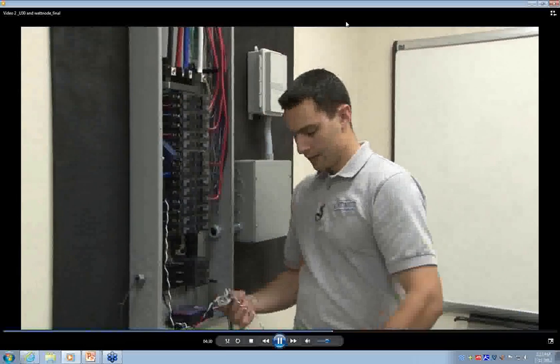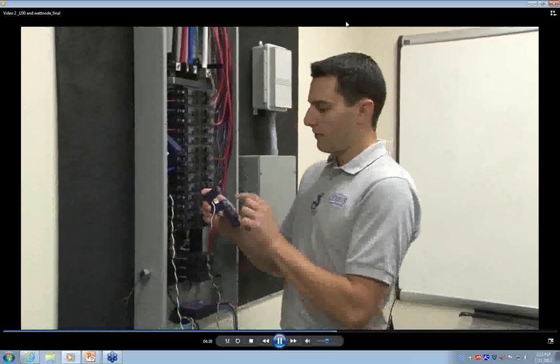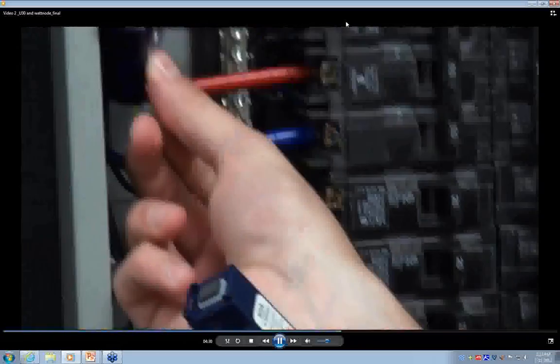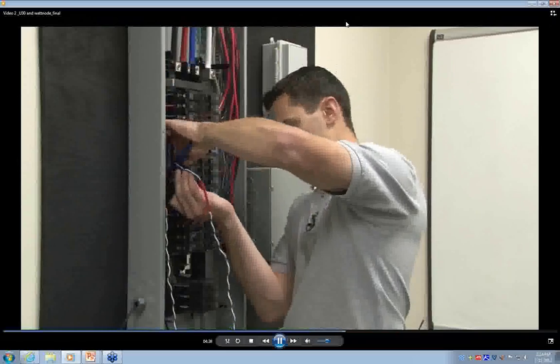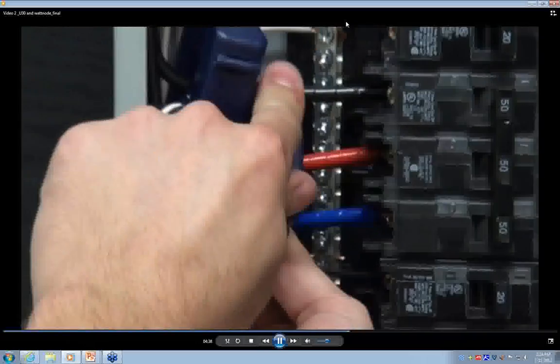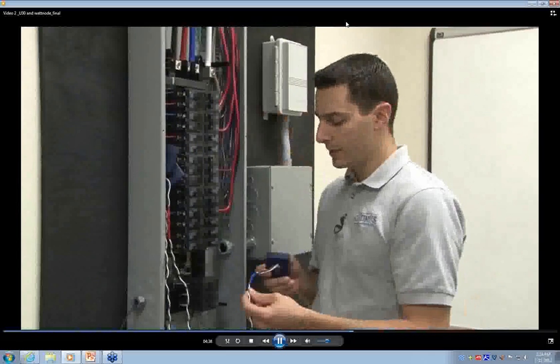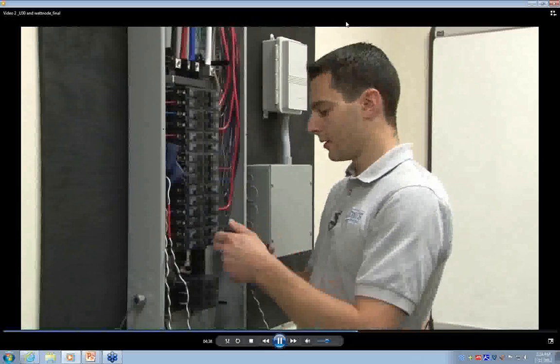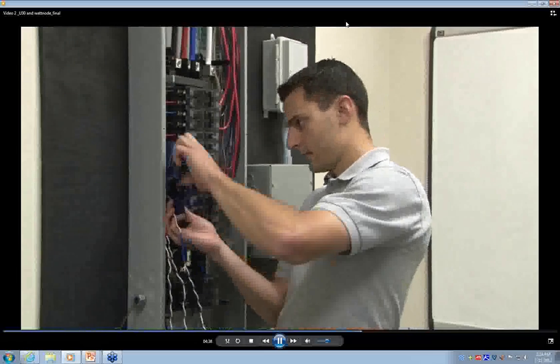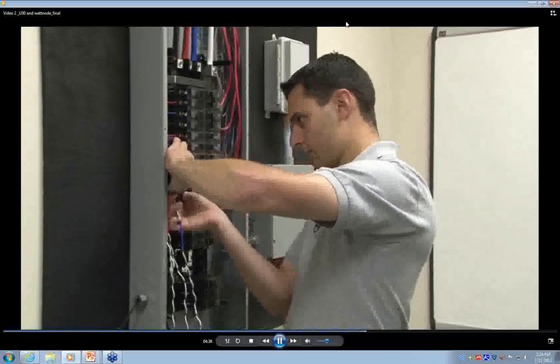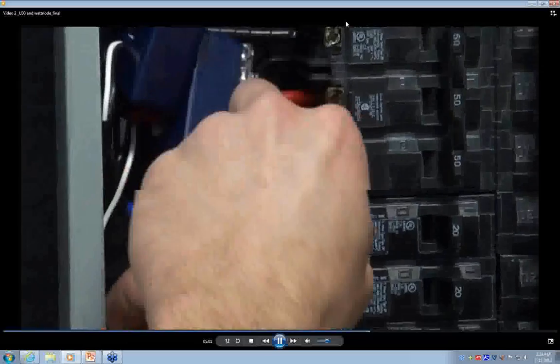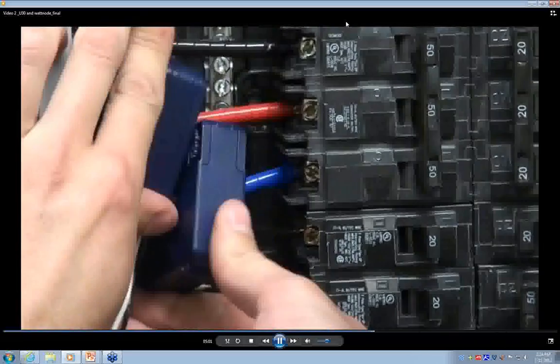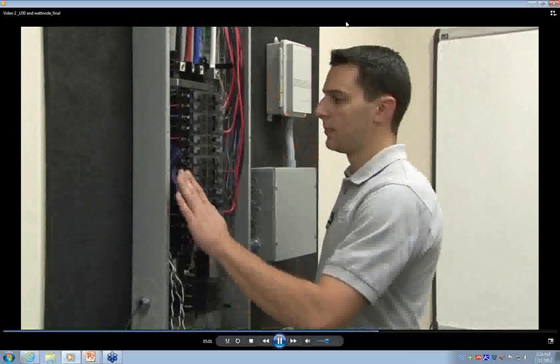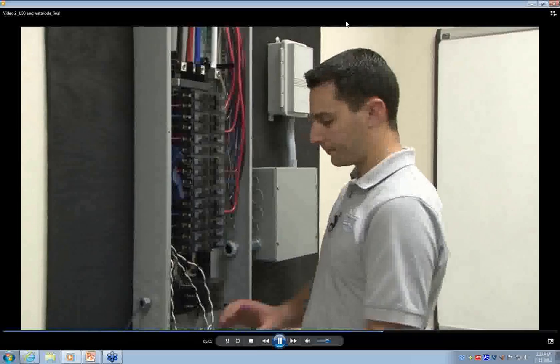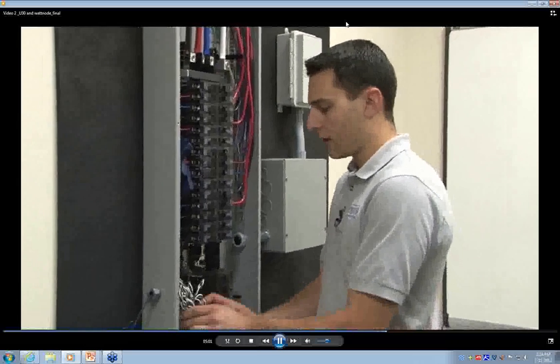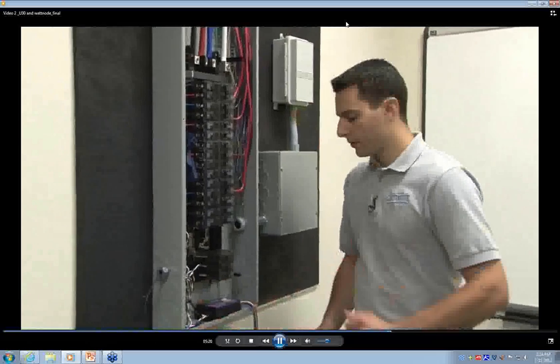We'll now move on to the red, phase B. Make sure the arrow faces the source, and this will go around the red conductor of our circuit. And lastly, our blue CT, phase C, will go around the blue conductor. And we'll want to tuck the CTs in deep enough to allow for the enclosure cover to be installed. We'll neaten our CT wires, and then we can move on to our voltage leads.